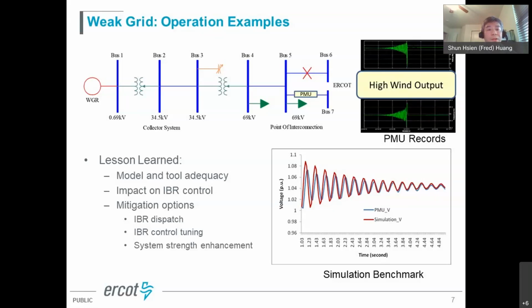Second, the controller becomes very sensitive when the system is in a weak grid condition, so properly identifying and tuning it became one of the challenges and practices we adopted. There are many mitigation options to make the project stable. One quick option we identified in real time when this event occurred was simply to reduce the output - managing the inverter-based output at a lower level can help stabilize the system response under weaker grid conditions.